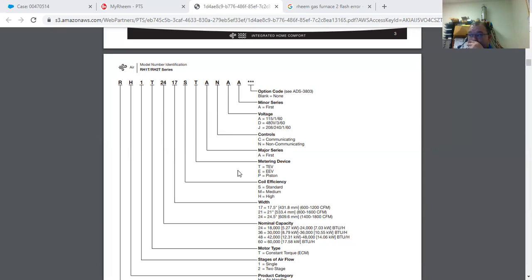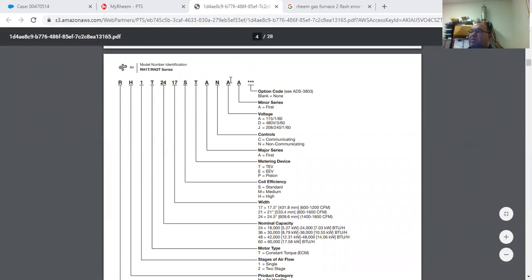We don't stock any piston models. Everything we stock either has the TEVs or the EEVs. The A is the major series. In this case here, the N stands for non-communicating. If it was a communicating air handler, which we'll not cover today, it would actually have a C. And here's your various voltages here. In this case here, it's listed an A, so this will be a 115 volt model. Normally what you'll see will be a J voltage, which is your 208, 240 single phase. Finally, the A stands for minor series. That doesn't really mean a whole lot to us in the field, but that's part of the model number. So if there's been any revisions, it would reflect that in the model number.